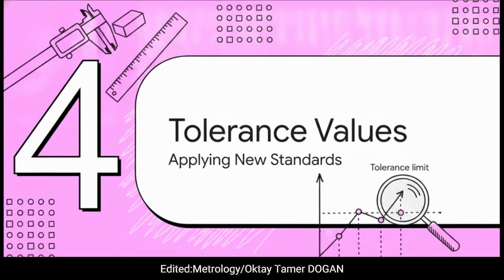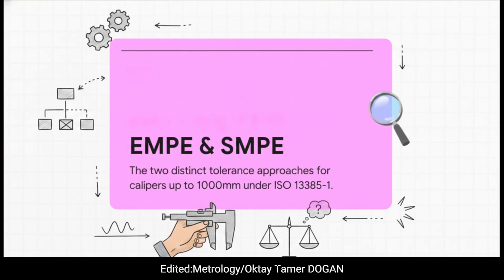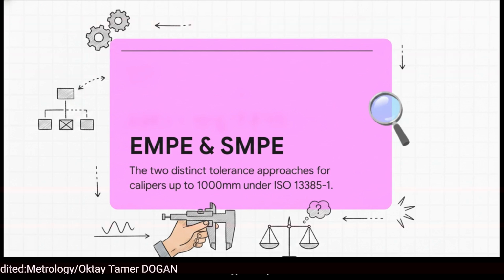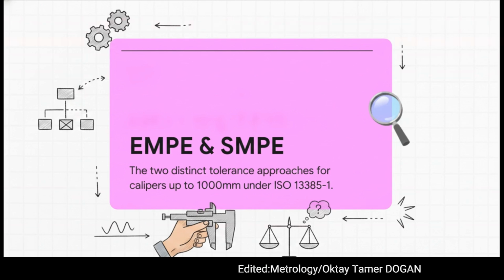All right, Section 4, applying new tolerance values. So now we've got our physical measurements, and it's time for the evaluation phase. We're checking our real-world numbers against the modern standard's allowable errors. Like we talked about earlier, swapping DIN 862 for ISO 13385-1 meant throwing out the old single-value system and bringing in MPE and SMPE. Remember, MPE is your absolute maximum permissible error, and SMPE handles acceptable error when the scale shifts. When assessing a device today, you've got to take a risk-based, user-focused approach to figure out which metrics and decision rules you and your client actually agree upon for their specific manufacturing needs.